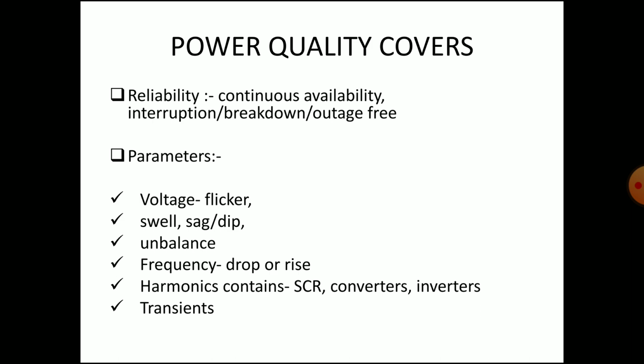So power quality covers reliability, meaning continuous availability of the electrical supply with no interruption, no breakdown, and no outage. So what are the parameters regarding power quality? That contains voltage flicker, voltage sag and swell, voltage unbalance, frequency unbalance, drop or rise, harmonic contents due to the SCR converters, inverters, and obviously the transients. These are the parameters that decide the power quality.